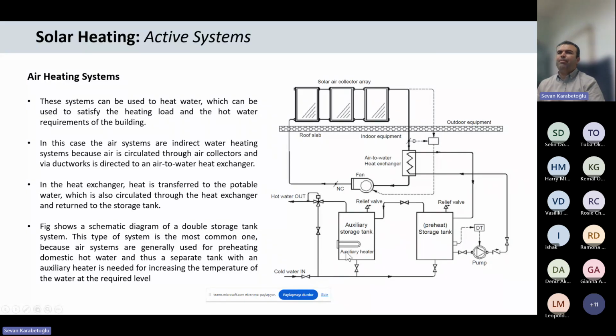Of course, if the demand is, for instance, warming up water, not for the space, and the mass flow rate is large for water heating, therefore an auxiliary heater should be implemented on the storage tank. Also, because of the intermittence of solar energy, the solar tank charge duration should be less. Therefore, the auxiliary heater, again with a control like PID control units, should supply the demands.